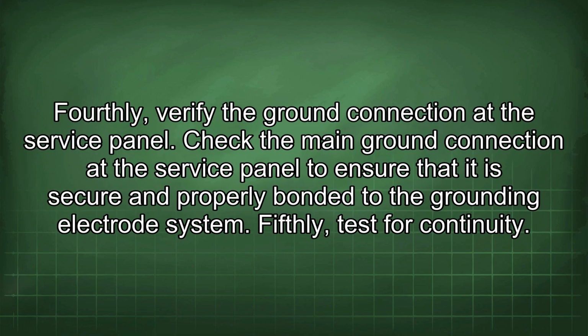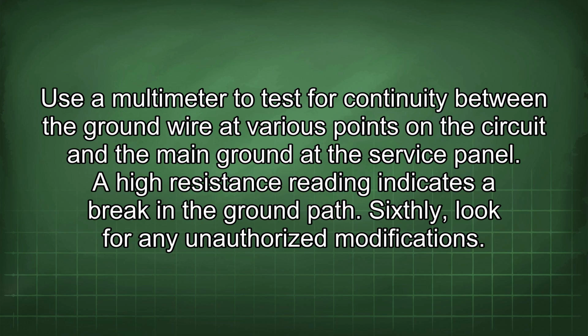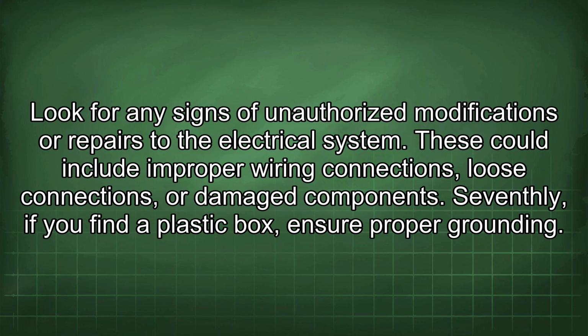Fourthly, verify the ground connection at the service panel. Check the main ground connection at the service panel to ensure that it is secure and properly bonded to the grounding electrode system. Fifthly, test for continuity. Use a multimeter to test for continuity between the ground wire at various points on the circuit and the main ground of the service panel. A high resistance reading indicates a break in the ground path. Sixthly, look for any unauthorized modifications. Look for any signs of unauthorized modifications or repairs to the electrical system. These could include improper wiring connections, loose connections, or damaged components.